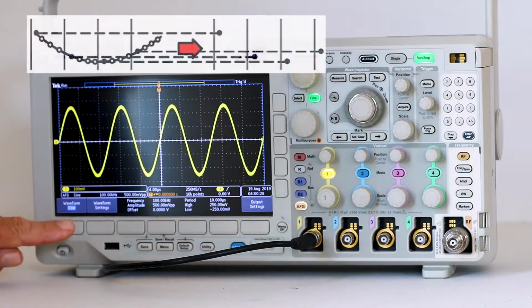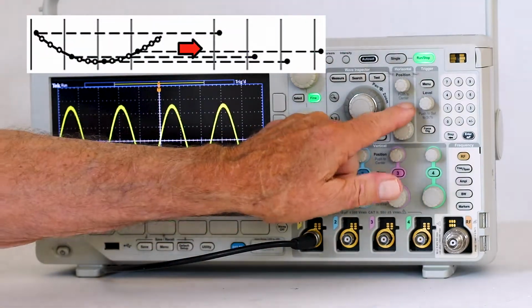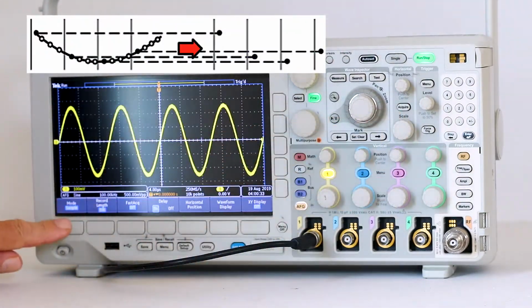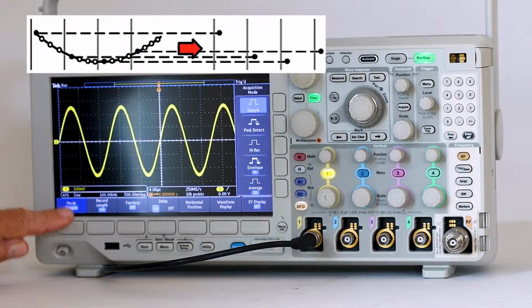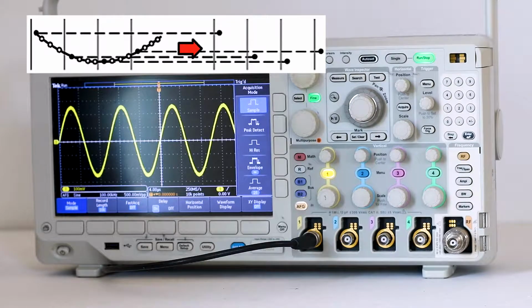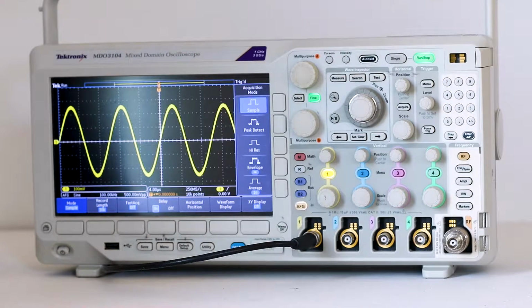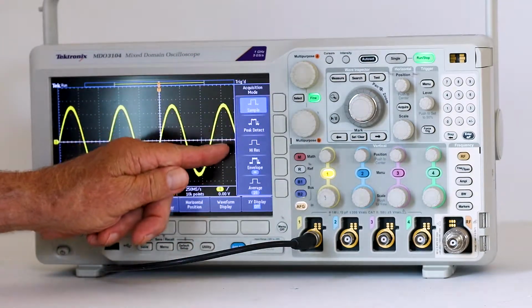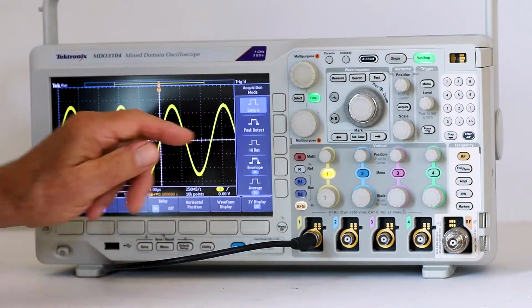Sample mode simply retains the first sampled point from each acquisition interval of the waveform that is displayed. Note that we are dealing with each acquisition interval, not each acquisition. Each waveform has a set number of acquisition intervals, and if they recur with sufficient frequency, the analog waveforms can be digitized with perfect fidelity in accord with the Nyquist theorem. The acquisition modes appear in the vertical menu at the right side of the screen.